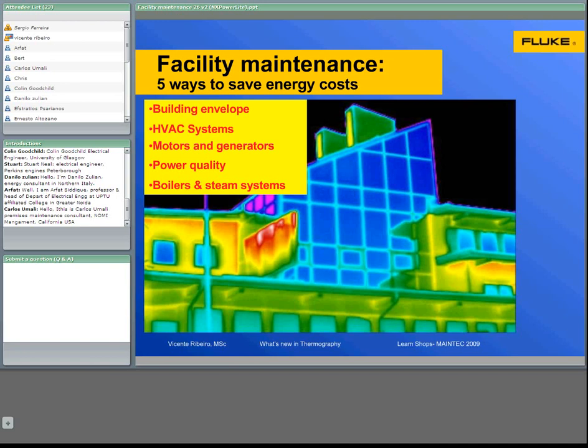One of the advantages of using thermography is that thermography is easy to use and it's very quick. We just scan the motors like we scan the motors with our own eyes, and we can see that the motor is not working properly. So we can do something about it. We can bring in insulation testers, we can bring in vibration analysis to see what the problem of the motor is. But it is important that we control the temperatures of the motors so that we can understand what the problems are.